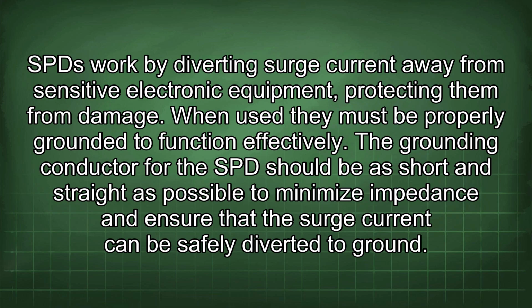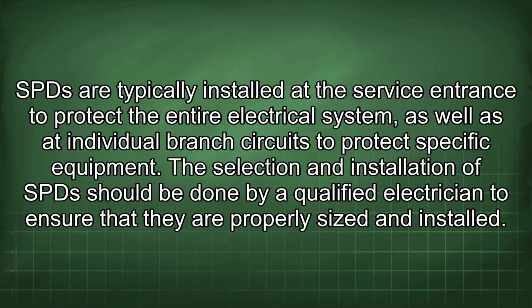When used, they must be properly grounded to function effectively. The grounding conductor for the SPD should be as short and straight as possible to minimize impedance and ensure that the surge current can be safely diverted to ground. SPDs are typically installed at the service entrance to protect the entire electrical system, as well as at individual branch circuits to protect specific equipment. The selection and installation of SPDs should be done by a qualified electrician to ensure that they are properly sized and installed.